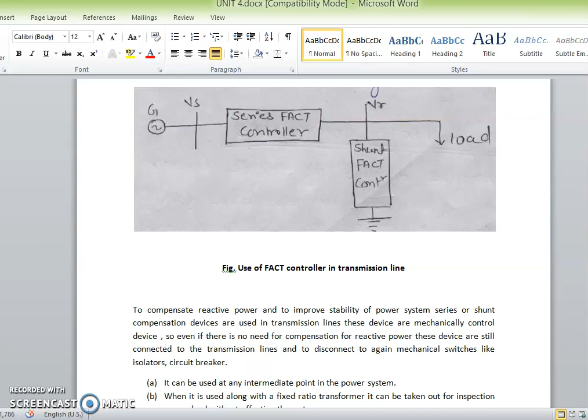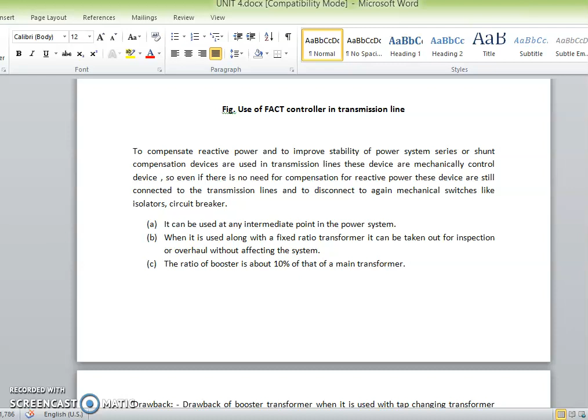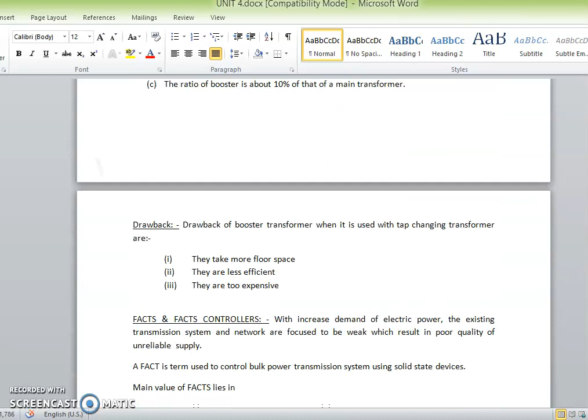When it is used along with a fixed ratio transformer, it can be taken out for inspection or overhaul without affecting the system. The rating of the booster is about 10% of that of the main transformer. And what are the drawbacks? Following are the drawbacks of a booster transformer when it is used with a tap changing transformer: they take more floor space, they are less efficient, and they are too expensive.